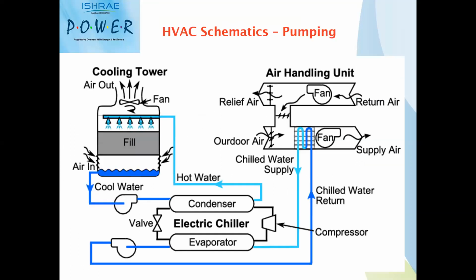So as we are all working in the HVAC industry, when it comes to a typical application side, where exactly are these pumps installed? Whatever pumps we are talking about, all the centrifugal pumps are for chilled water application, where we'll be having a plant room where we have a chiller. So in a typical plant room, we have these evaporator pumps, which are called primary. And on the load side, we'll typically be having secondary pumps as well as tertiary pumps. I'll take you through in a couple of slides ahead what type of schemes we have in a typical HVAC system.